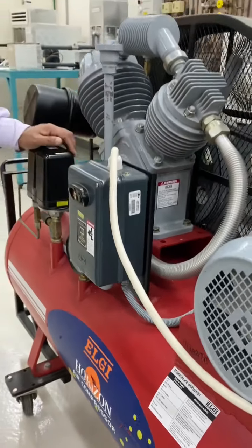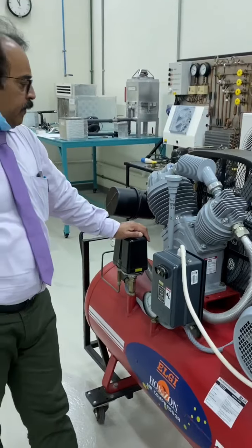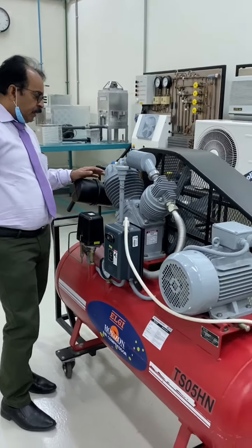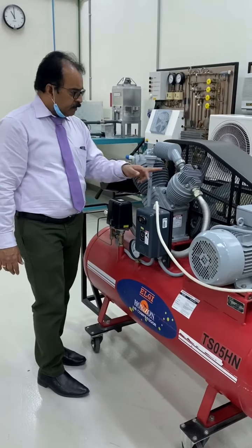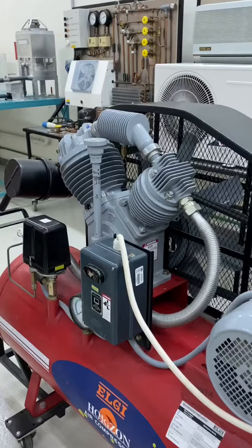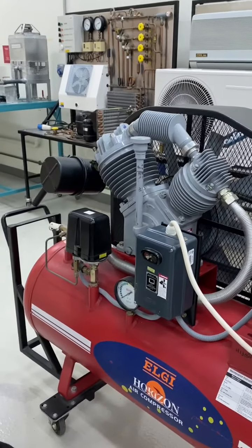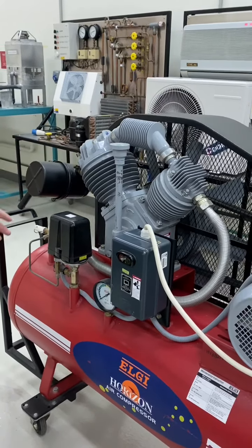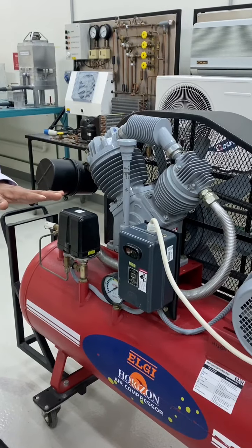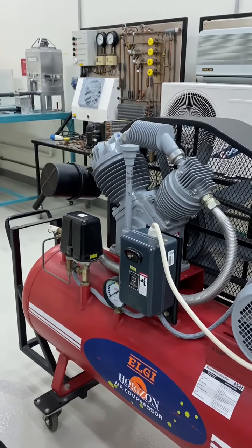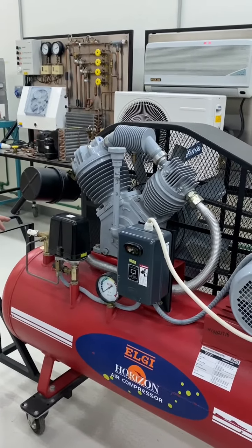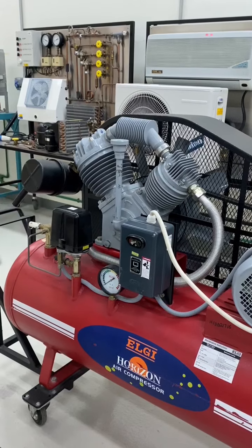So what maintenance do we do? The important thing is we check the outer parts for any damage on the outer body, and also check the gasket here, and the pipe connections. We also check whether the safety valve is working properly by running the machine and making it reach 12 kilogram force per centimeter square. When it becomes 12 kilogram force per centimeter square, the motor must stop. The machine should stop. If it doesn't stop, something is wrong with the safety valve. Then you need to set the safety valve.